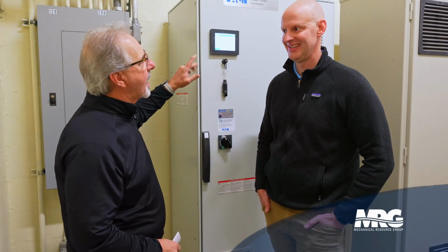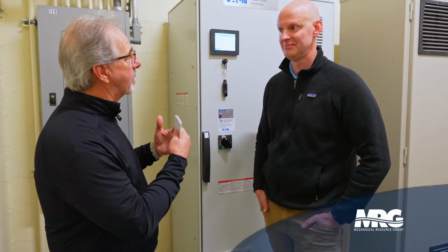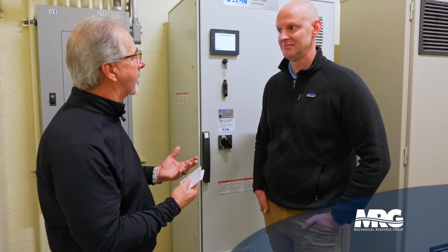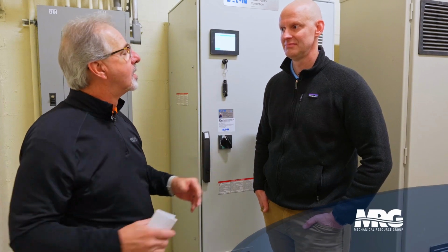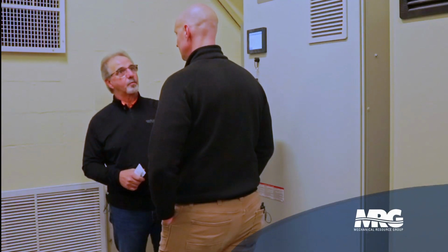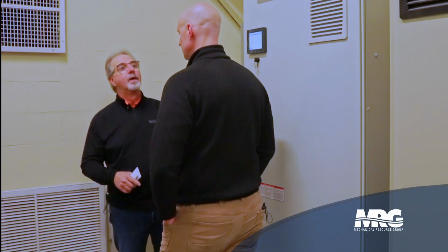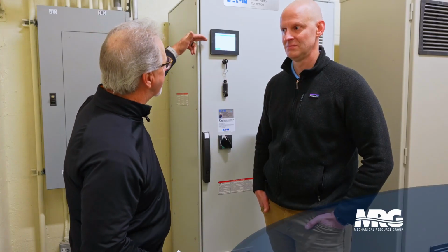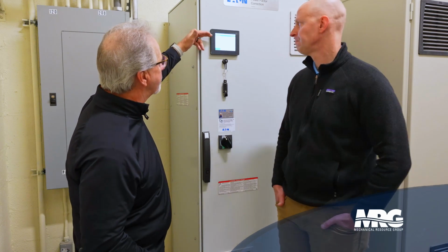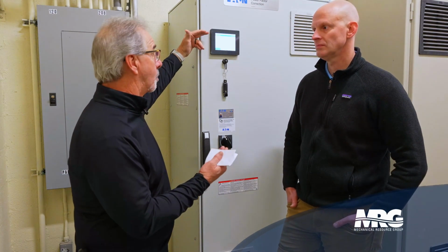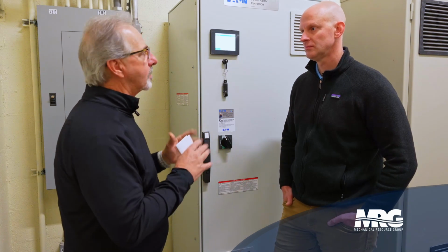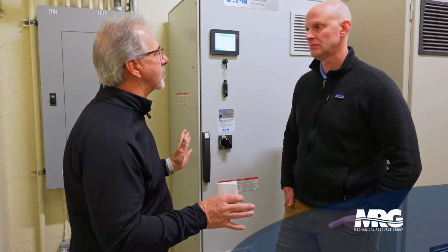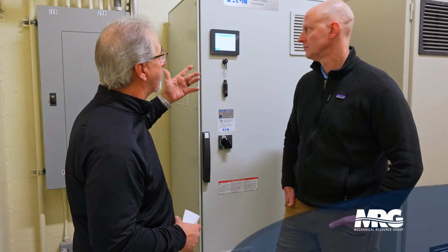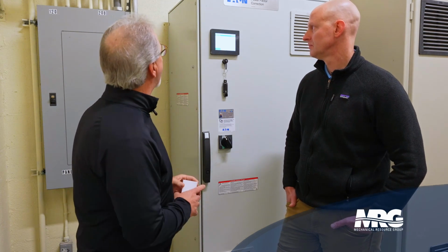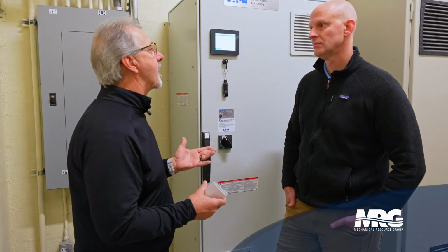Okay, so John, what we have here now is the active filter. This is the part that we were talking about outside, about attenuating the harmonics and being good neighbors. What this actually does is it captures that remaining harmonic that we did not capture through the impedance of the drive itself, and it takes that and filters it. And if you'll notice up here on the screen, it gives me a total load. Well, right now I'm only running one pump. It's a Friday afternoon. Everybody's at work. Not a lot of people using a lot of water. So we're only running one pump, and we're running it fairly slow. I'm only drawing an average of about 240 amps, okay?